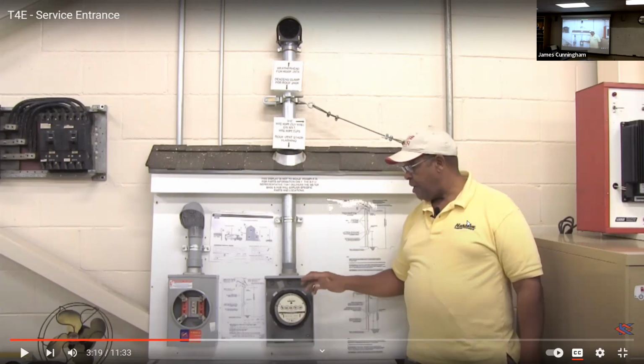Because now, most of the time with the arc fault circuit breakers, you're going to need a panel that's going to need at least 40 breakers. Used to be that we could divide the breakers into what I call splits, where there's one breaker spot, you could have two separate breakers in that slot. Can't do that anymore. With the arc faults, you need a slot for each breaker. So the panels are much bigger, and you still have your meter built into the panel also most of the time, instead of doing it that way. You just buy one box, one panel, and everything goes in there. Your circuit breakers, your meter, everything is all in one.